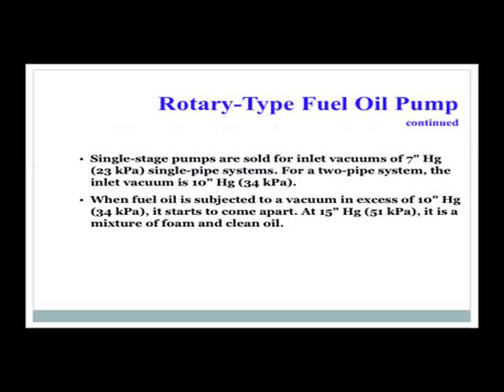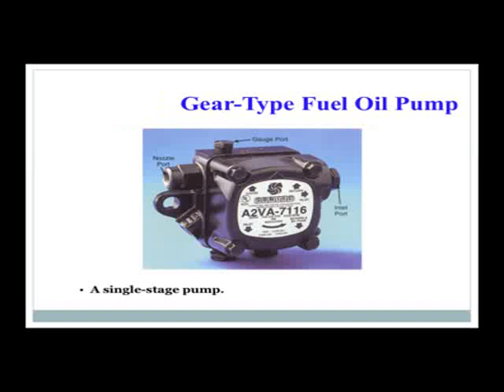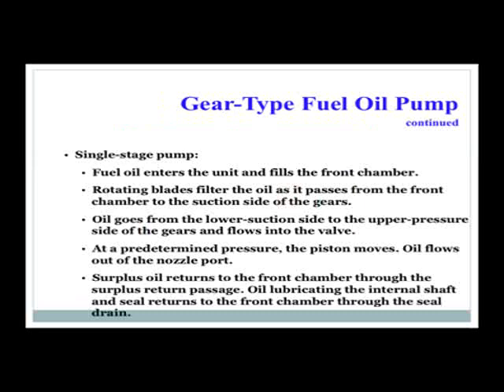When fuel oil is subjected to a vacuum in excess of 10 inches mercury, it starts to come apart. At 15 inches mercury, it becomes a mixture of foam and clean oil, which does not burn well. The gear-type fuel oil pump is also a single-stage pump. The fuel enters the unit and fills the front chamber. The rotating filter blades filter the oil as it passes the front chamber to the suction side of the gears. Oil goes from the lower suction side to the upper pressure side of the gears and flows into the valve.